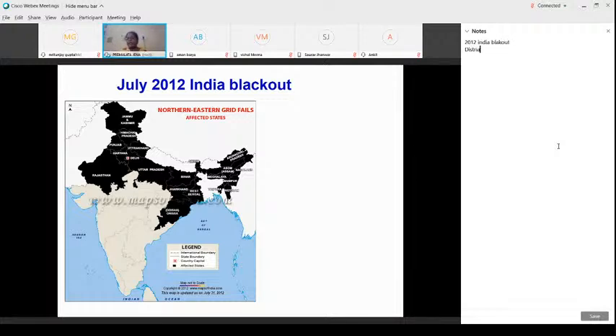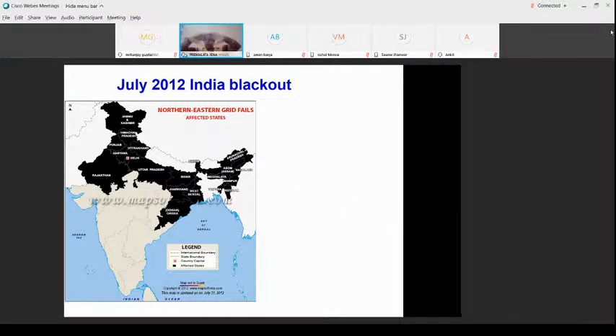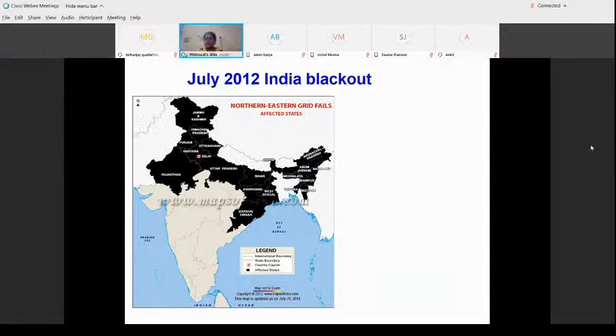So what happened? That line was carrying definitely some 400, the exact figure I do not remember. Because it's a 400 kV line, the carrying capacity is in the range of 200 to 600 megawatt, not kilowatt. So that amount of power, what will happen? According to KCL, the current and the power will take some other path because it is an interconnected network. It is not a single line. Many lines connect the western grid to the northern grid. So other lines started carrying the power, they became overloaded, and again those lines tripped. Slowly, all the lines tripped.